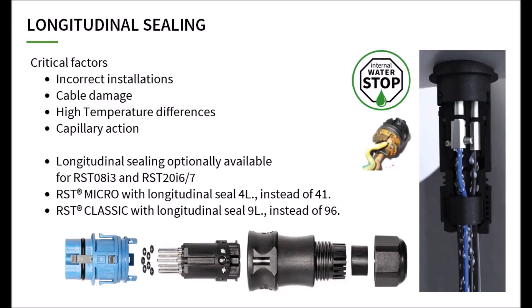An often underestimated phenomenon occurs due to the capillary effect of pipes. If, for example, a line is defective at one point and water can penetrate, the water will be drawn through the line right into the connector. This happens faster than expected and over long distances. However, not only injuries to the lines, but also an unprofessional installation at the other end of the line can lead to this situation.